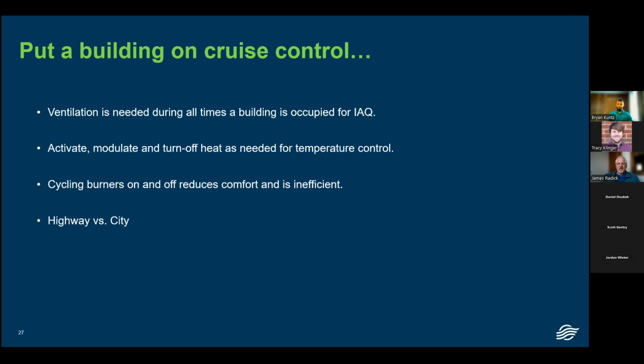And I like to stress the words air management, because that's what positive pressure allows you to do. You want to set up your air management system so it acts the same way. Doors open, doors closed. Bring in more outside air, bring in less outside air. As heat loss in the building increases or decreases, the system actually modulates. Now, how does it do that though?